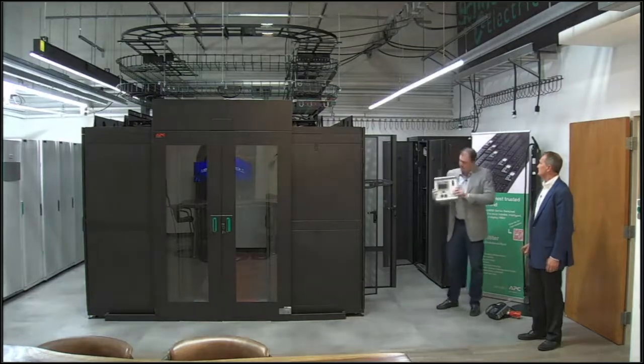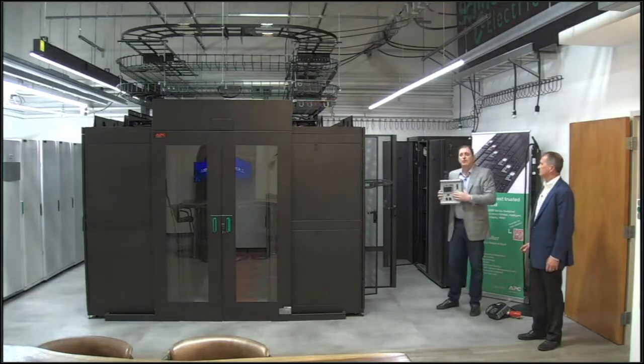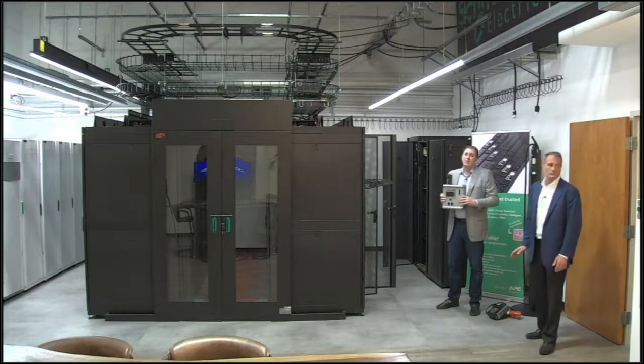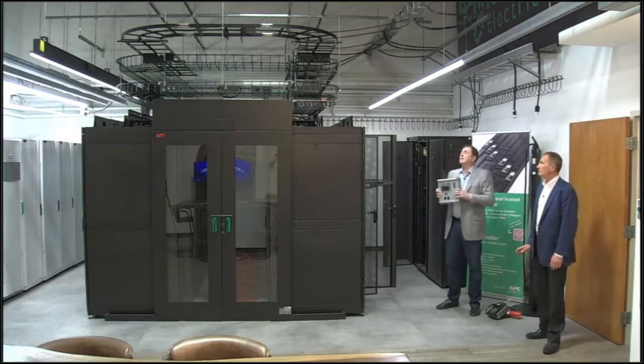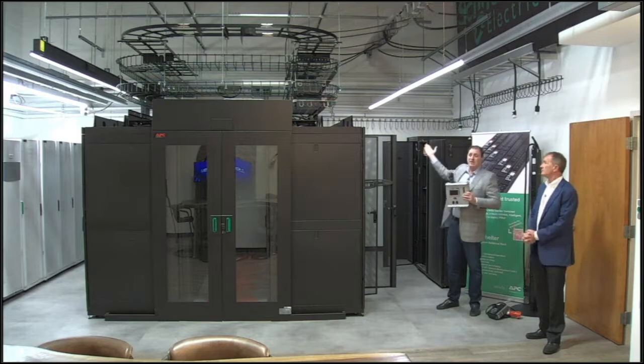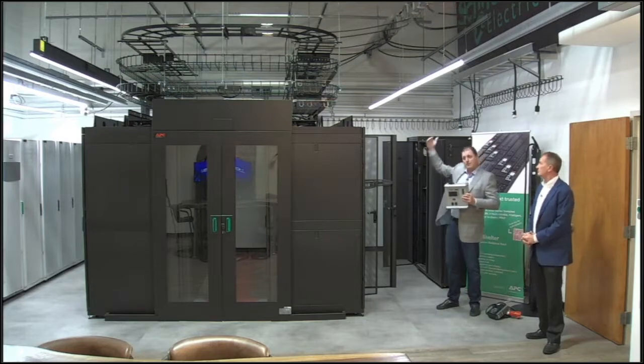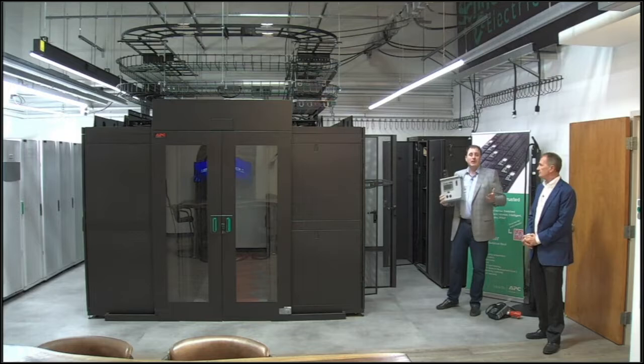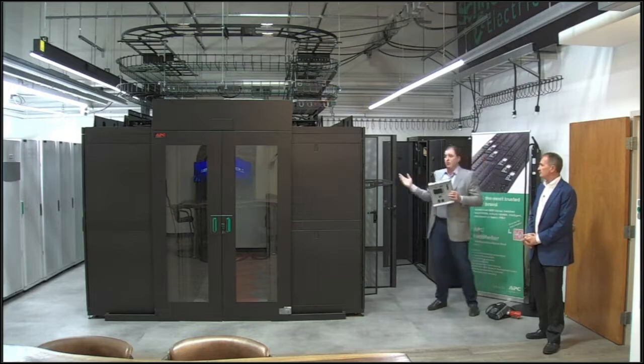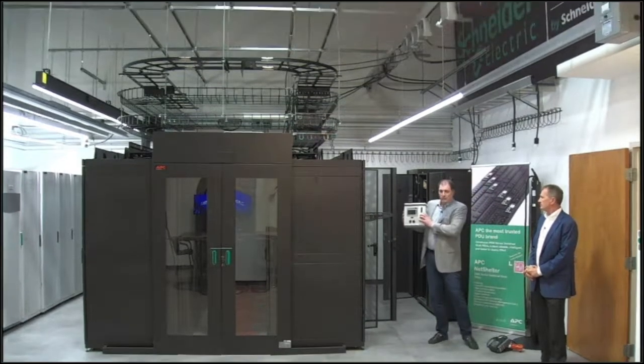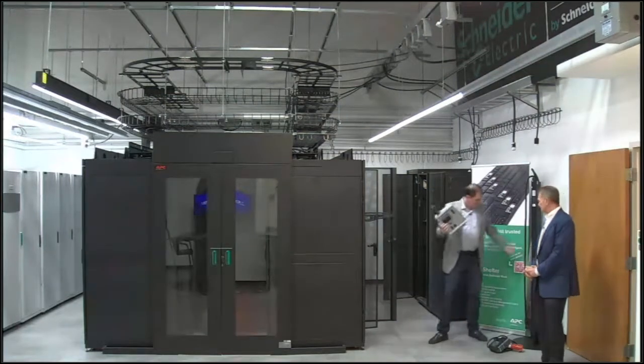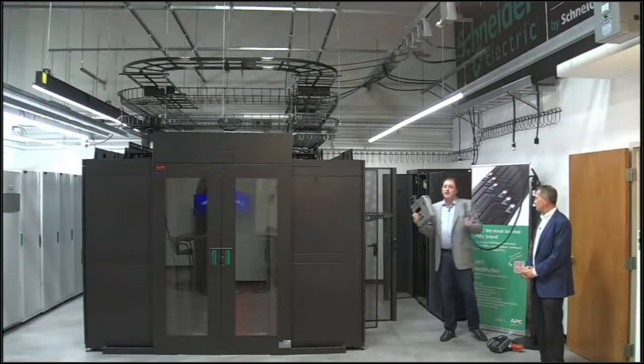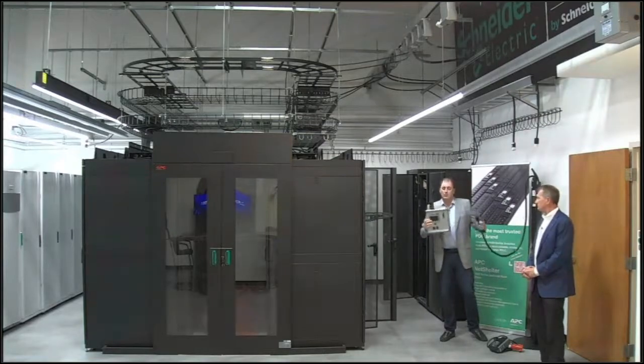This box can have whatever combination of circuit breakers or fuses you need to power the data center. It may or may not have a cord off it. If you look above us, you'll see we've got cords coming off ours because of where the busway is. Often, though, the busway is directly over a row of racks, and this box would look as such—it wouldn't have a cord. It would sit right above the racks, and the pigtail from the in-rack PDU would plug directly into it.